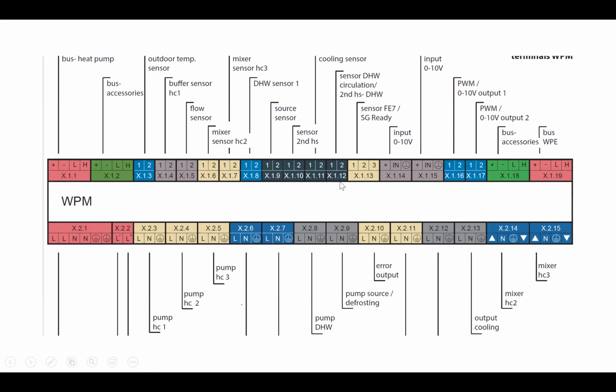X113 - if we go into the commissioning on the WPM, we can go into the commissioning menu and go into what's called the IO configuration. I'll actually do it in a minute and show you guys. We can say we want that terminal, X113, to act as an off-on switch. All we have to do is link 2 and 3, and the system will turn from standby mode into programmed operation, or from eco mode into programmed operation.